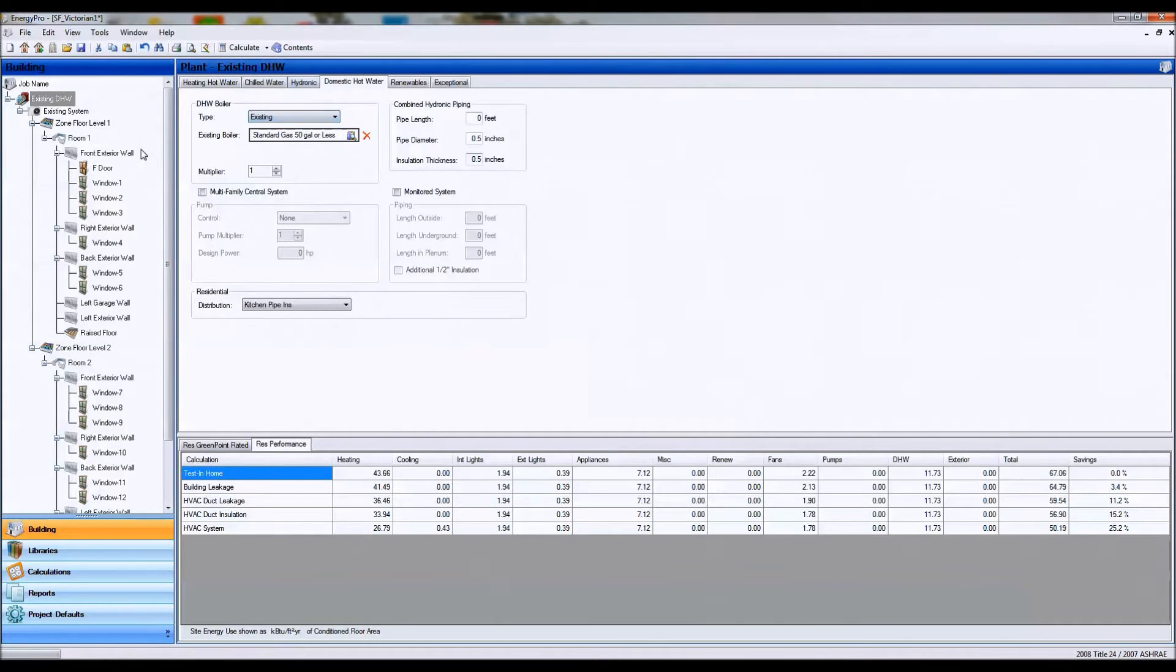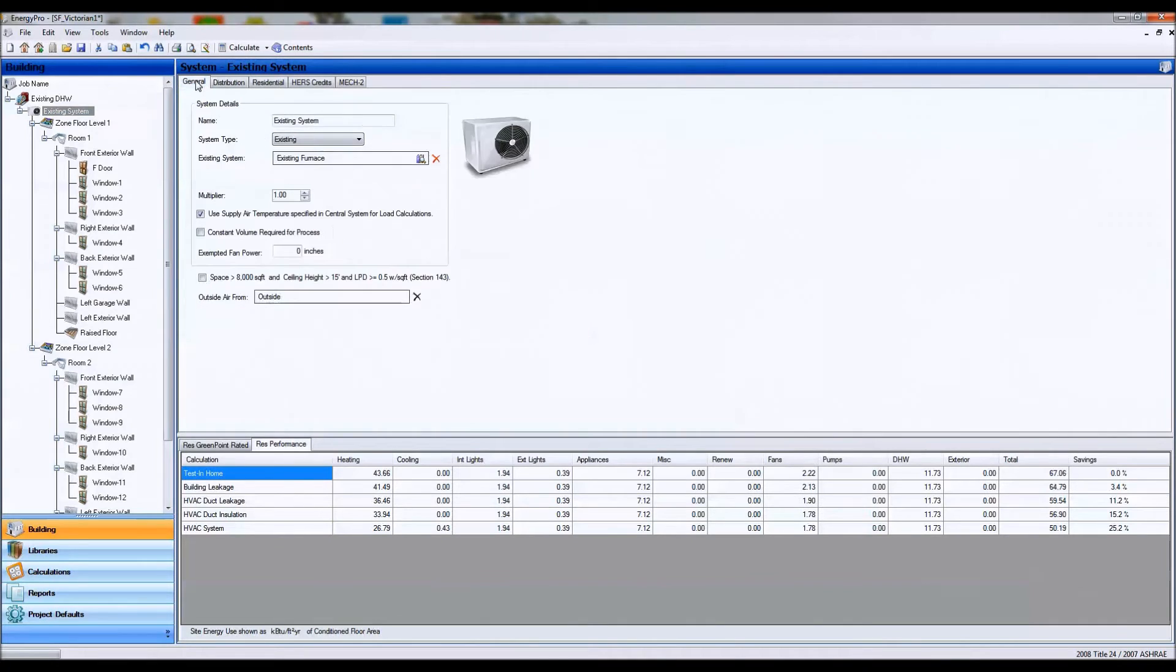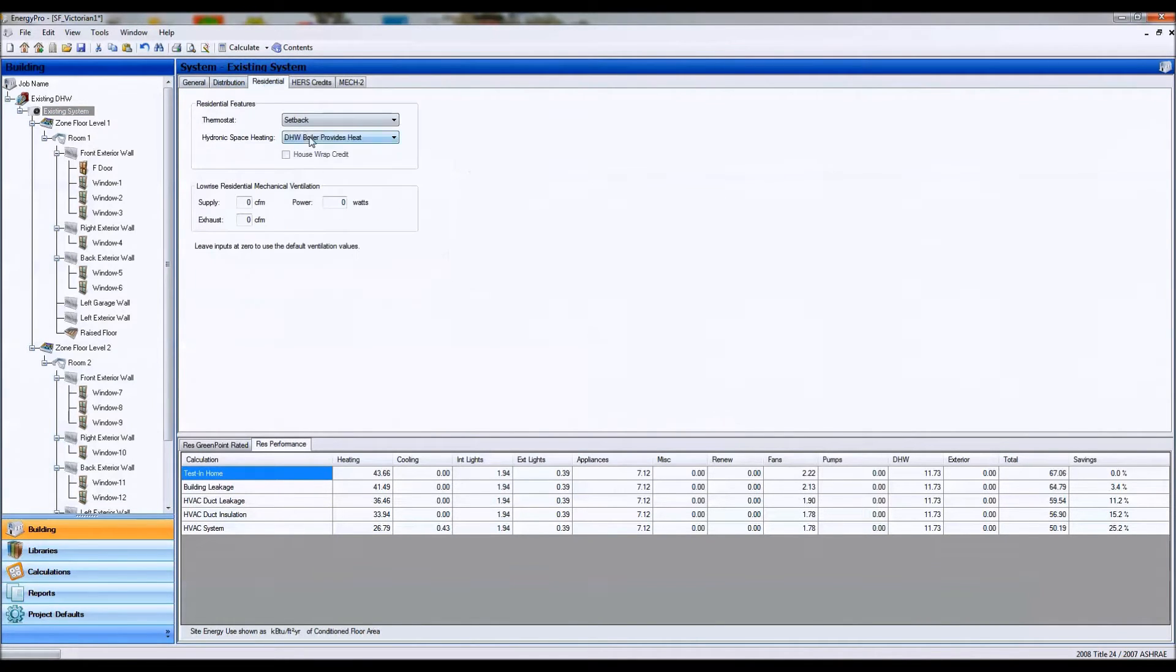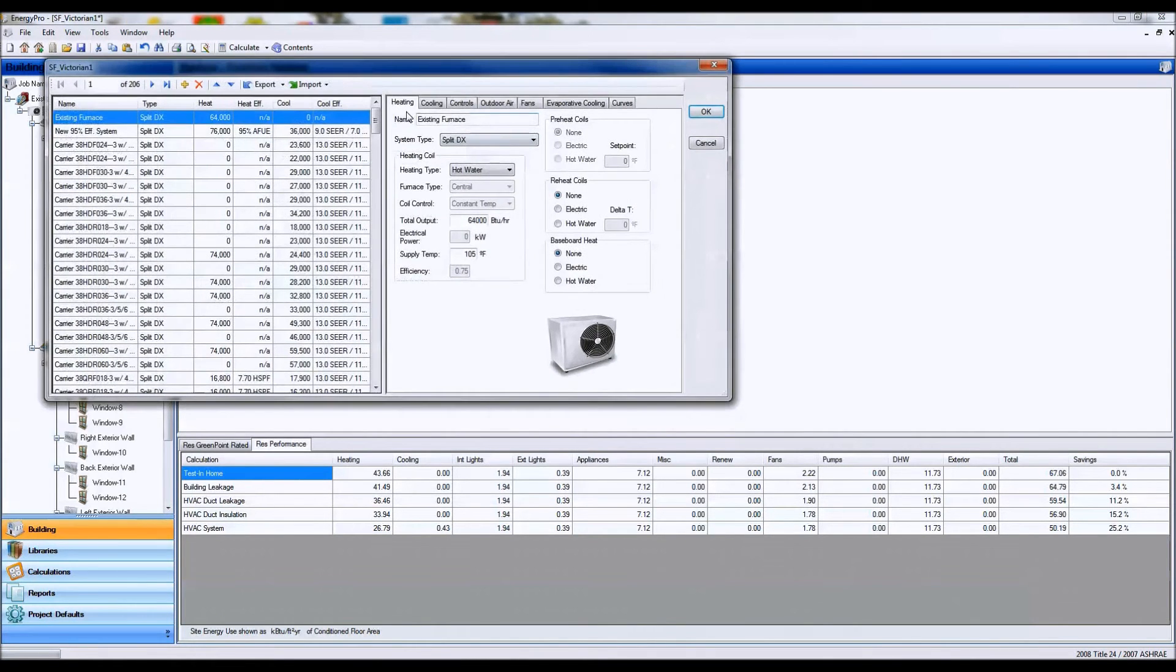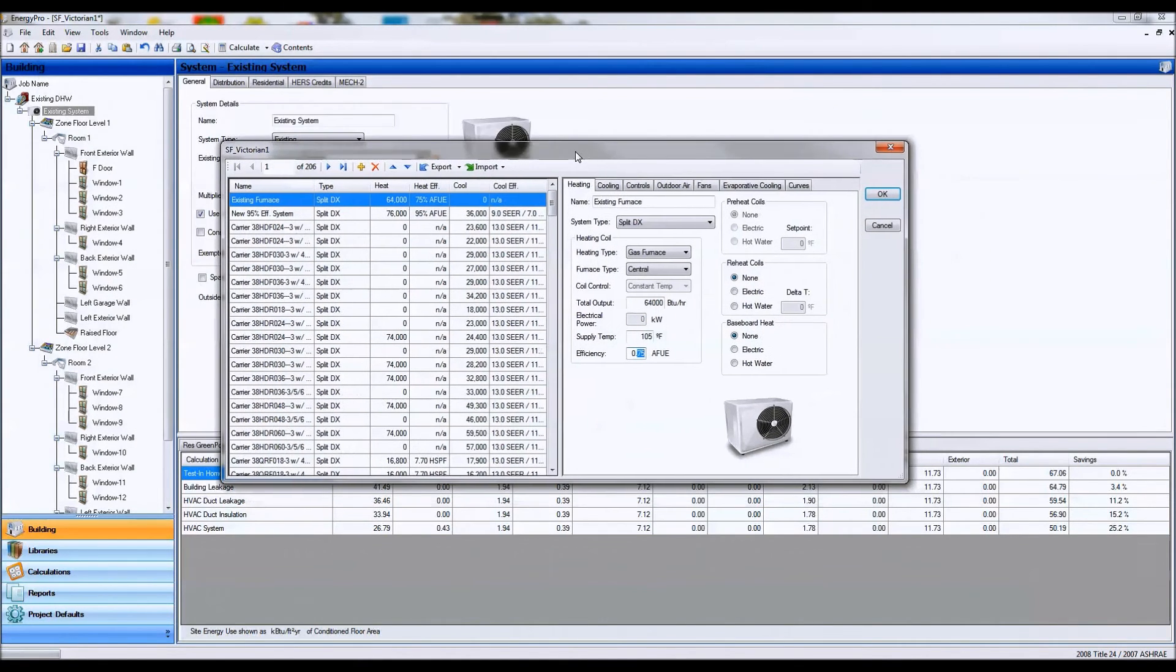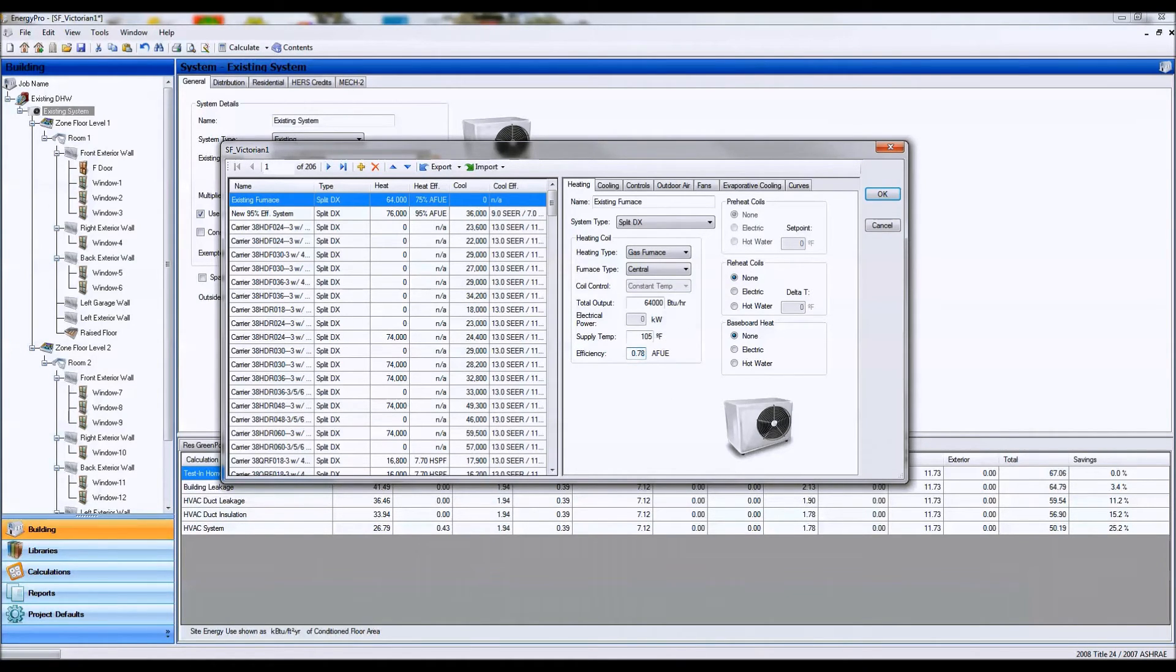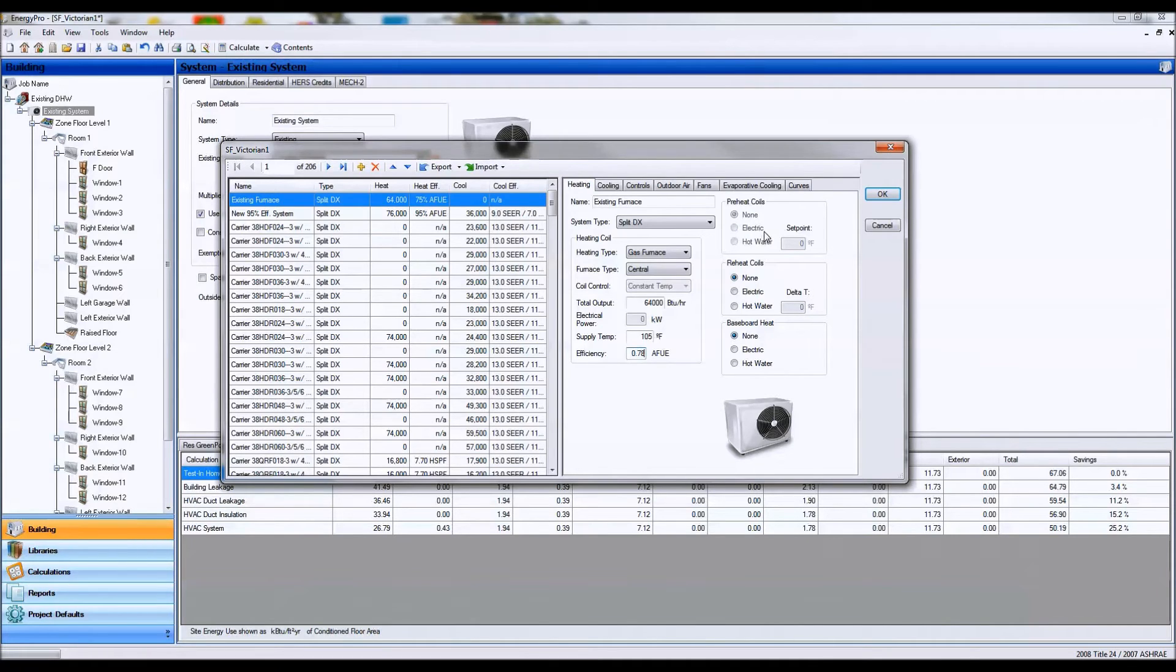There's another approach for modeling the heating side using combined hydronic systems, and that's by leaving that as none on the residential tab, going back to the general tab heating section, setting this to a gas furnace, and then just go ahead and put in the AFUE based on the energy factor or the recovery efficiency. So let's say we had a, our large storage water heater had a recovery efficiency of 78%, so we're going to go ahead and put that in as our recovery efficiency of our existing system, and that's our, this could be our hydronic air handler or our baseboards or our radiators.